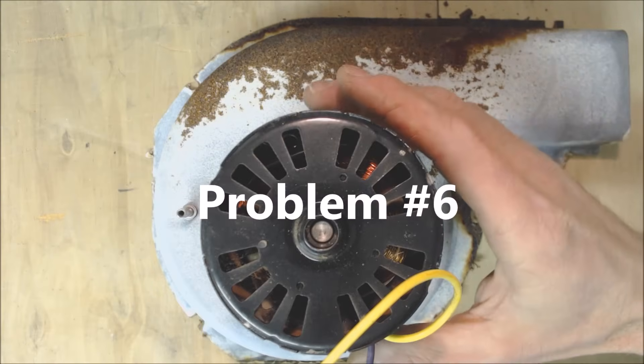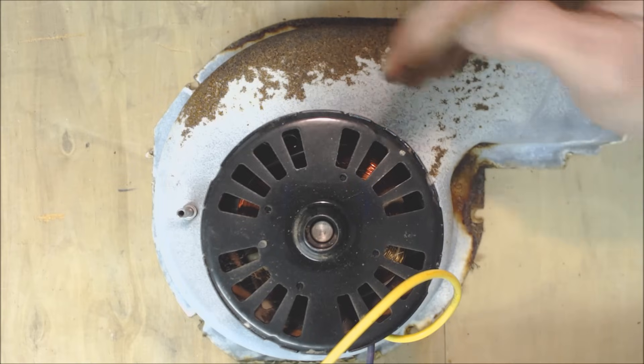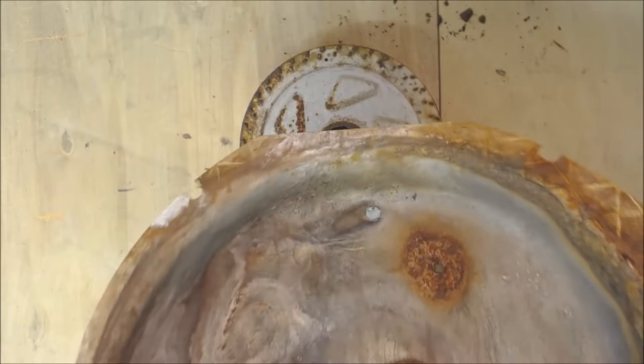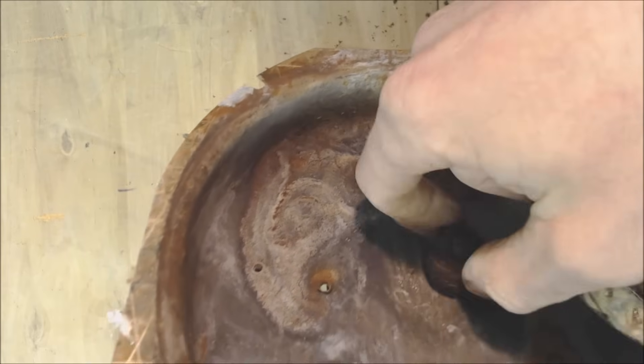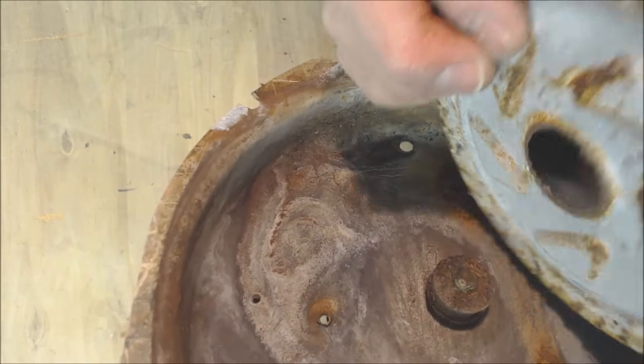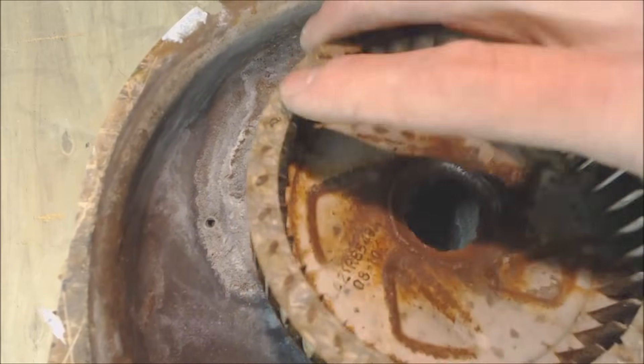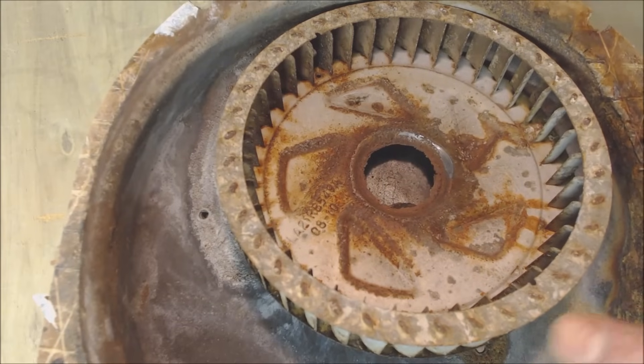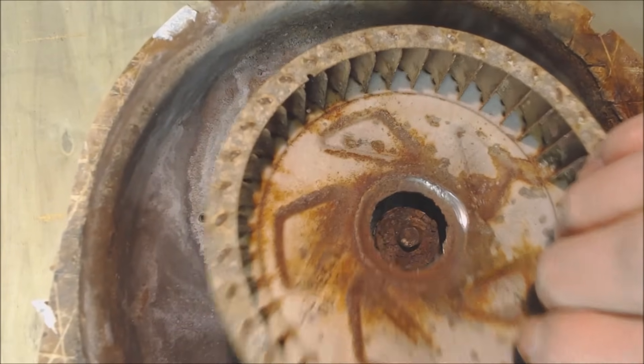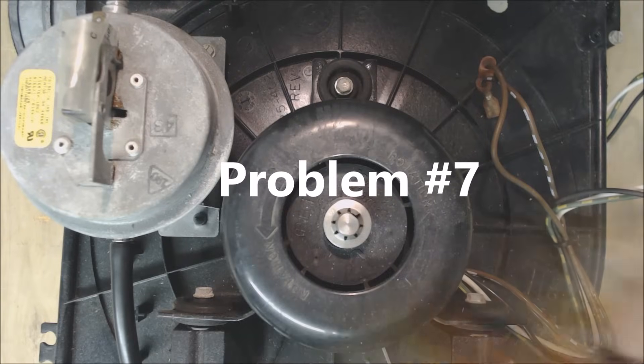This is problem number six. In this case, once again, the inducer motor is out of a package unit and the problem with this one was that the inducer wheel actually has fallen off completely due to rot. So it's rusting and just rotting the metal right there and it's coming completely off. You could have something like this that's metal but you can even have plastic ones where these actually all fall apart on the inside and then jam up the wheel and then basically you need to replace this or replace the entire housing.